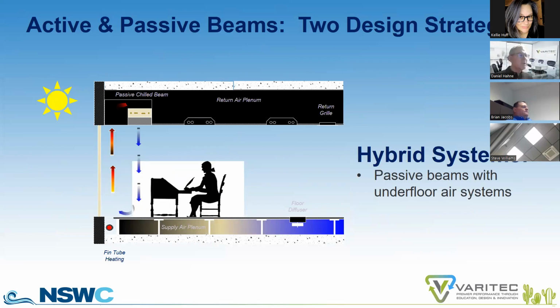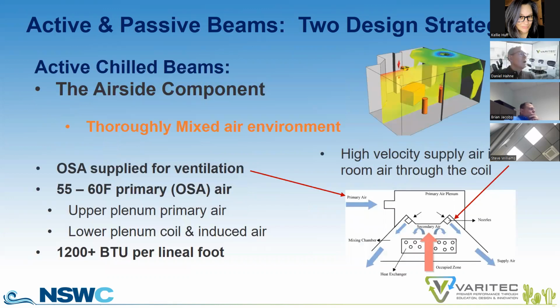Here's an example of a 100% outside air underfloor system with a passive chill beam at the perimeter zone. This is very compelling because you have outside air locally injected, only outside air injected in the occupied zone. And I'm confident that indoor air quality within that zone would be very, very interesting to look at and to evaluate. So how does an active chill beam differ from a passive chill beam? Well, as discussed briefly, there is an air side component. An active chill beam is ducted for airflow, unlike a passive chill beam.